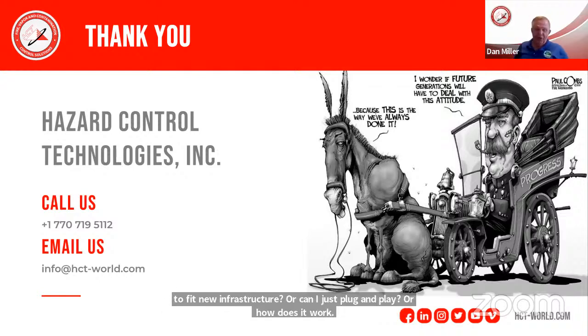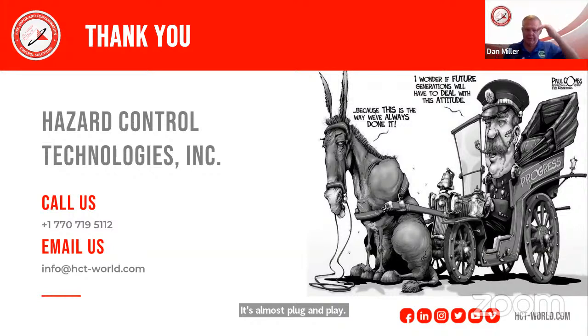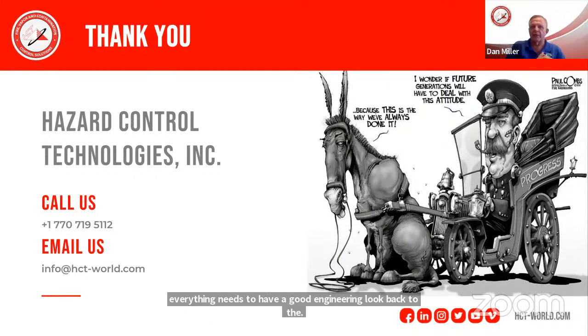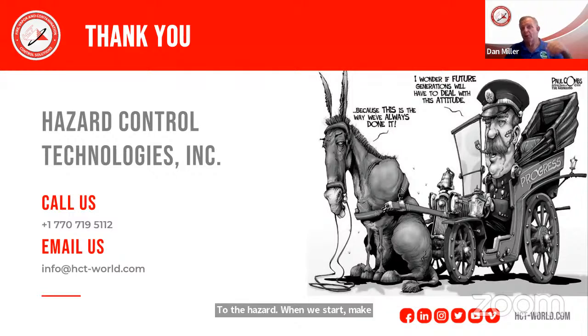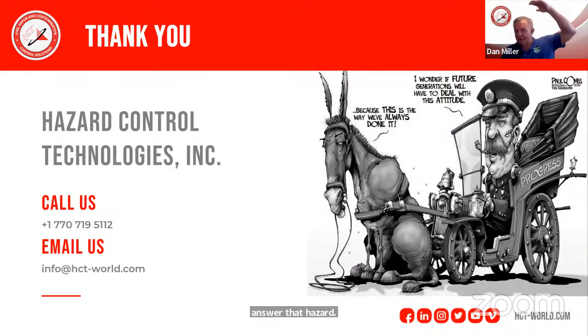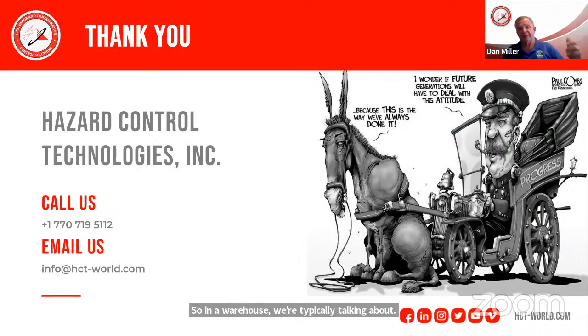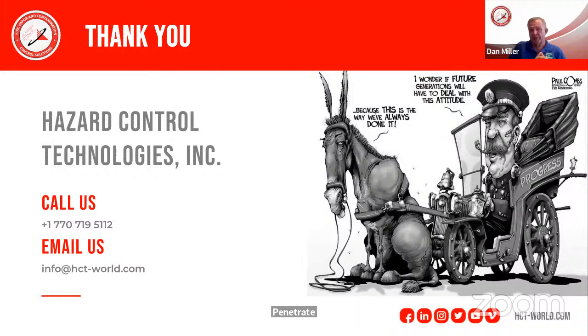Well, it's almost plug and play, but everything needs a good engineering look back at the hazard when we start, to make sure we're going to answer that hazard. In a warehouse, we're typically talking about high-ceiling warehouses with ESFR sprinkler heads 40 feet off the ground, where water has an inability to penetrate very well. F500 has an ability to penetrate deep down, and because of its high molecular weight, it does a pretty good job of reaching the floor quickly without floating around or being carried away by convection currents.